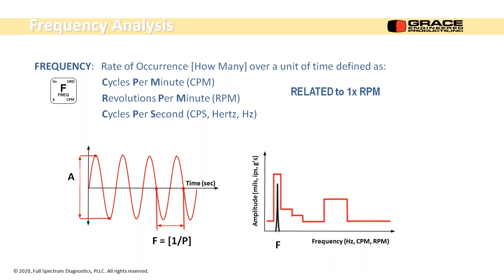So the way to probably do this would be on demand or at the beginning or end of a run cycle, capture a full spectrum and store it in the database. Otherwise, you can continue on with just the amplitude levels, the overall amplitudes. But as we talked the other days of this series, how do you calculate a frequency from a time waveform? You have to encapsulate the entire period in time. So we start here, we go to a negative maximum, we go to a positive maximum, and then we go back to zero and repeat.